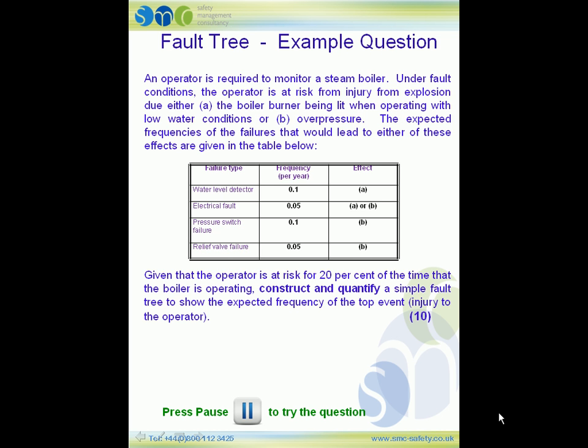For condition B — over pressure — there are three conditions: the electrical fault again at 0.05 per year, the pressure switch failure at 0.1 per year, and the relief valve failure at 0.05 per year. Given that the operator is at risk for 20% of the time that the boiler is operating, you have to construct and quantify a simple fault tree to show the expected frequency of the top event, which is the injury to the operator.